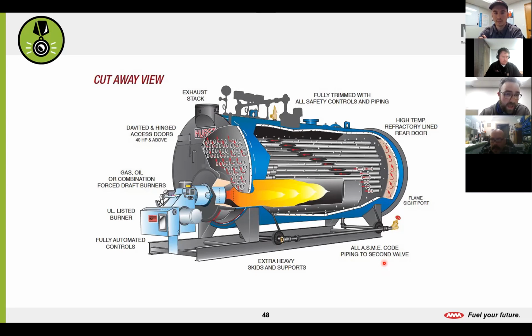And if you look at this tank, this is called a fire tube burner. The reason it's called a fire tube burner is because the flame is contained within these tubes here, and then it's surrounded completely by water. So the way the operation works here is our flame comes in, goes through our main barrel here, hits our back plate here, and comes back in these smaller tubes here, travels through, comes back to our front plate here, and then this up here, right here, sorry, don't know if that was visible or not. This is our flue exhaust. So this is where our exhaust gas exits that boiler here.